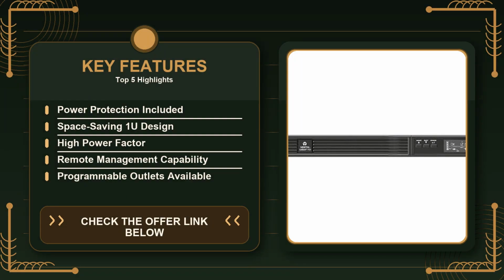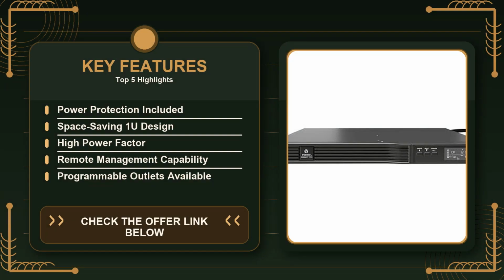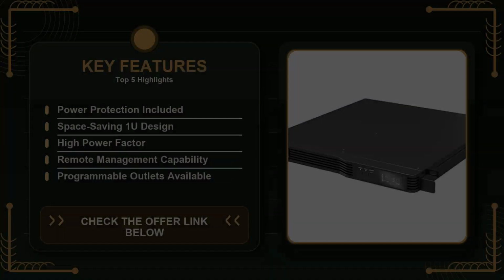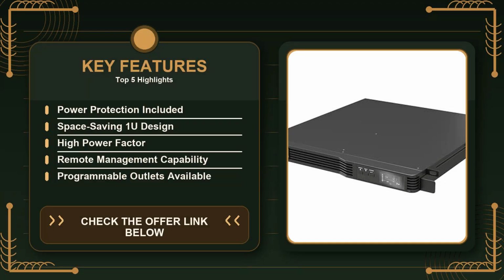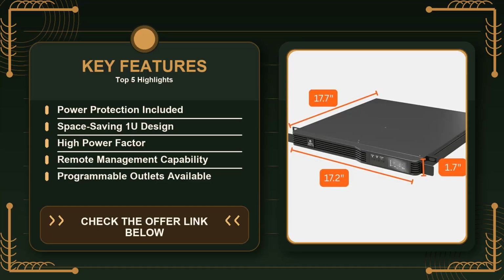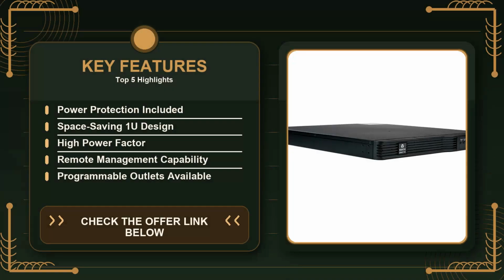From a maintenance perspective, the battery is user-replaceable but not hot-swappable, as mentioned earlier. The manuals stress regular battery testing and replacement every 3 to 5 years, which is standard for most UPS units. If you're comfortable scheduling a brief maintenance window once a year to check battery health, that's manageable. If you need truly zero downtime battery replacement, you'll need to look elsewhere. The upside of the PSI5's remote management is also a bit of a double-edged sword.